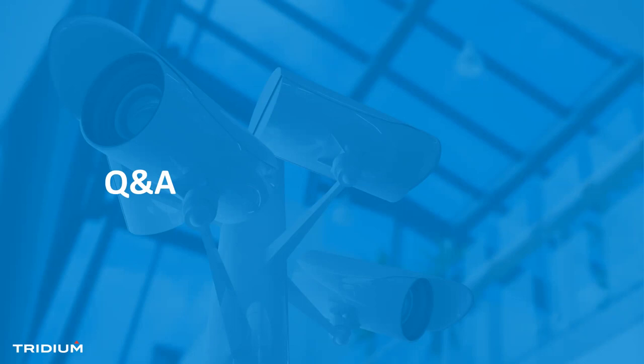Brad Truax, anything you want to add based on your experience? He explained that properly, and you've got to pay attention to your resources on those controllers when you're doing the interface directly to the JACEs, because there's a limited amount available. But these are extremely flexible devices that can do a lot. I've been very impressed with what they can handle, but you just have to pay attention to your resources when integrating more than one system at the JACE level.